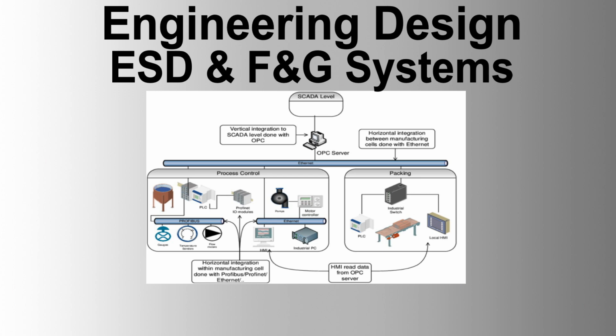3. Discrete inputs. Sensing voltage of 24 volts DC at 0.1 amps, incorporating contact bounce suppression. Capability to handle various types of switches and push buttons. Line monitored design for non-fail-safe inputs, galvanic isolators for intrinsic safe signals. 4. Discrete outputs. Powered outputs to DC solenoid valves, matrix panel LEDs, beacons, and relay coils. Individual external voltage sources for each output point with surge protection, arc suppression, and fuse disconnects.